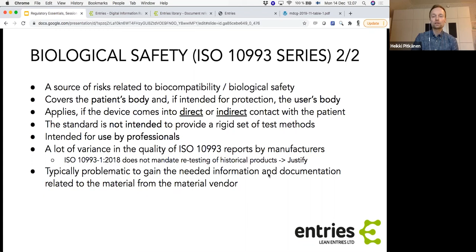And just like clinical evaluation, this one is also intended for use by professionals. So you should have a toxicologist or someone to sign off your biological safety report, and hopefully to plan it as well. Many larger companies go wrong in this area as well. There has been a lot of variance in the quality of these reports in the past, and it is beginning to align with the new version of the standard, which is a very good standard. It does not require that you redo all the testing for any historical products, but you can provide justification instead. A very problematic thing is gaining the needed information from the material providers and your vendors. Let's talk about this in a separate session in more detail.